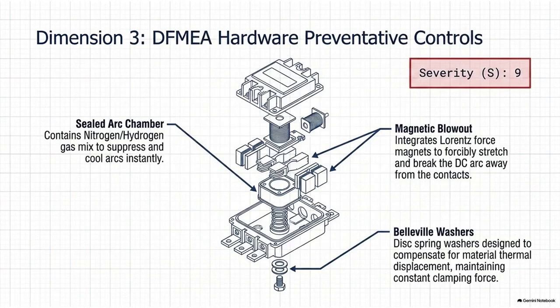Because nitrogen is fundamentally an inert gas. It lacks the chemical properties to support combustion or rapid oxidation. Okay, so it suffocates it. Right. By entirely replacing the reactive oxygen with inert nitrogen, you drastically reduce the arc's ability to burn the contact materials. Furthermore, the specific gas mixtures have excellent thermal conductivity properties, helping to rapidly cool the plasma. It creates a chemically suffocating environment for the spark.